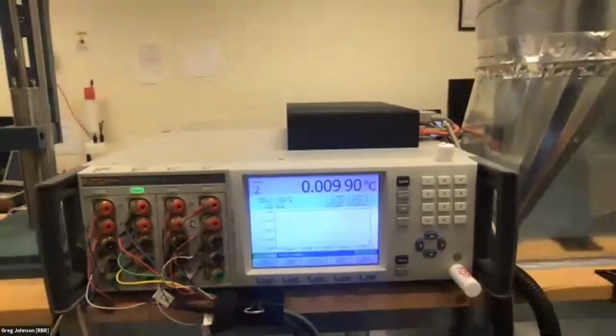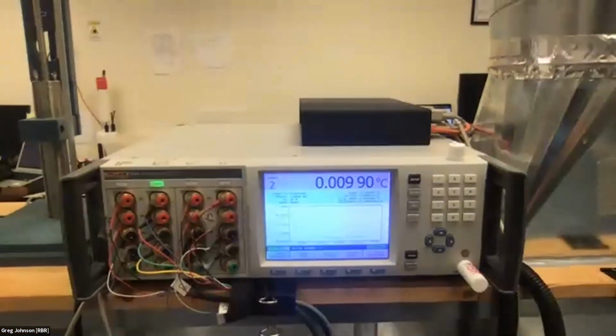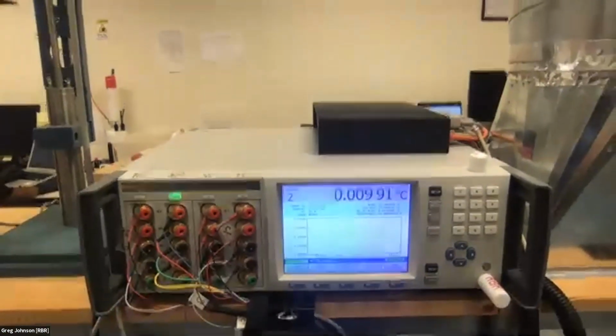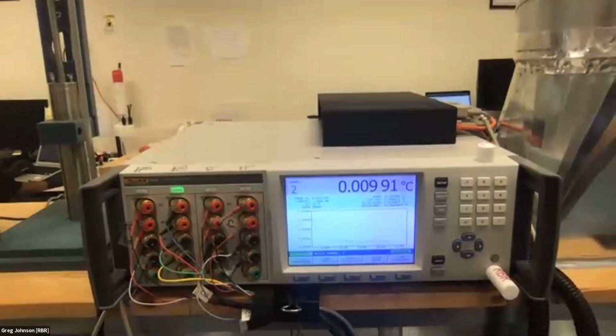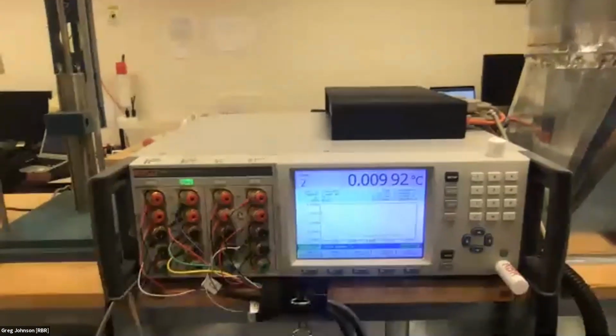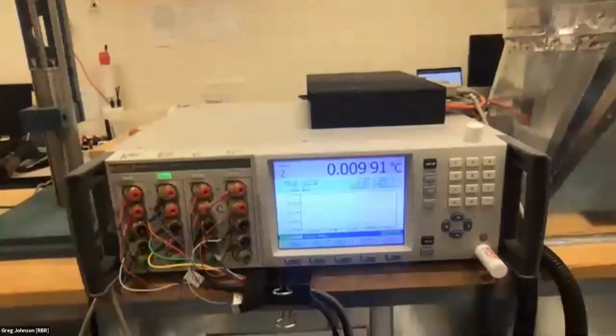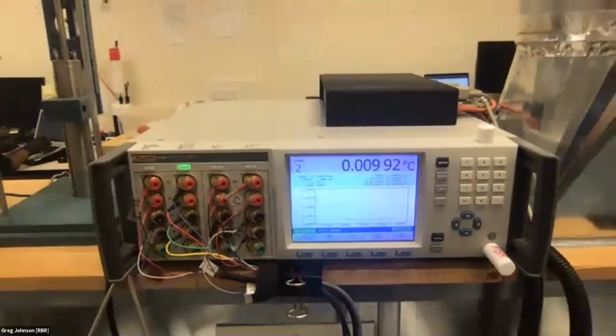Because we've just opened up the tank, we've got a bit of a jump on our temperature readings here. But you can see on our thermometer that we're getting very, very stable results. So this is just being used to calibrate one of our SPRTs at the moment, but because we've just disturbed it, it's a few micro-K off. So temperature we typically do, I'll tell you more details in a second as we do that.